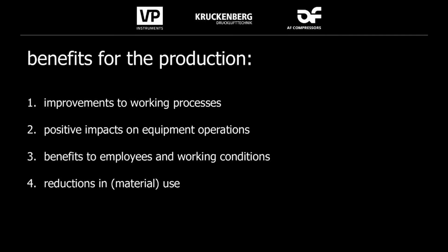on the production side. This customer had a hydraulic press for their product, but the opening and the closing process for this hydraulic press was realized with pneumatic cylinders, 16 cylinders in a row. The first one is filled, and then the second one is filled, because they were in line, each one after each other. And in between, the process was really hot and very loud, so workers could not stand next to it normally. And only with ultrasound, we were capable of documenting that there are a lot of leakages inside the single cylinders.